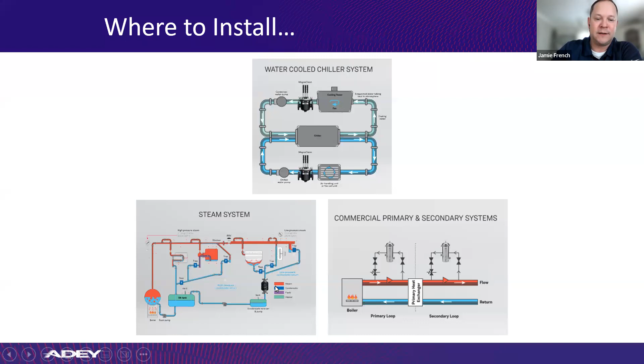We've got a lot of these in the Midwest at manufacturing facilities that use process steam, and they're just filtering their return water right before the condensate receiver, which protects the pumps on the condensate receiver. If you think about it, all that magnetic debris coming in, we can pick it up beforehand.